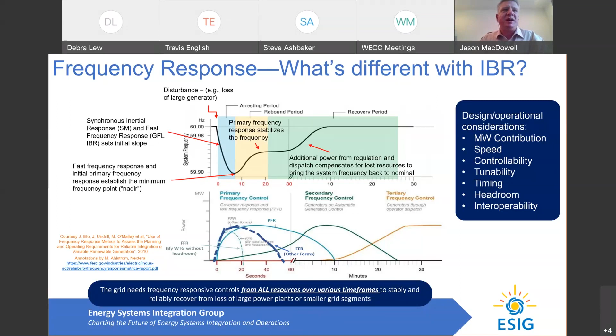The more you can inject, the quicker you can arrest that initial decline, and eventually coordinate with the primary frequency response of governors in conventional generation and the active power control in inverter-based resources to recover the frequency and automatically balance things out. We'll talk a lot about that initial decline and how we support frequency in the first several seconds, and coordinate that with primary response and recovery over tens of seconds. Coordination of all these capabilities is critical to actively support grid stability. Deepak will talk more about coordination of this control in his talk.